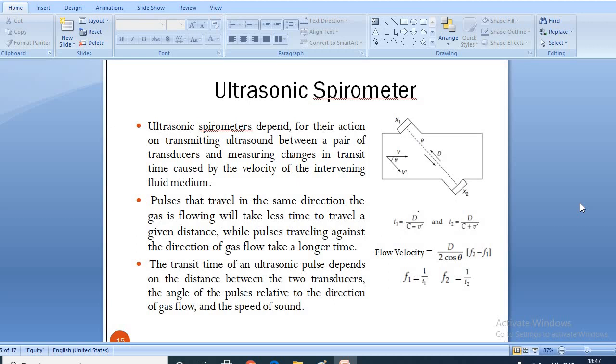The third type is ultrasonic spirometer. Ultrasonic spirometers depend for their action on transmitting ultrasound between a pair of transducers and measuring changes in transit time caused by the velocity of the intervening fluid medium. Pulses that travel in the same direction the gas is flowing will take less time to travel a given distance while pulses traveling against the direction of gas flow take a longer time.